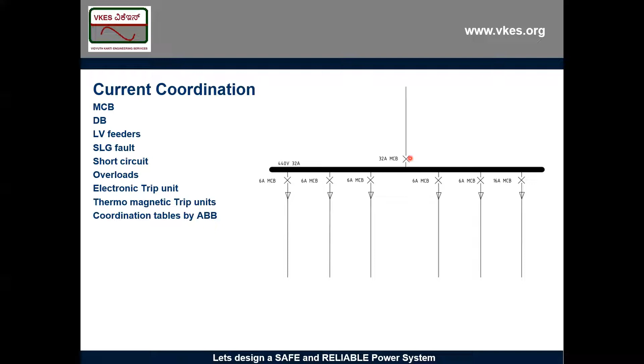And coming back to this time coordination. See here, the coordination is based on time. It means if there is a fault here, first this guy has to trip, then this guy has to trip, then this guy has to trip. One by one, they have to trip. That is why I'm using the word coordination. If there is a fault here, if this downstream breaker trips at, let's say, 100 millisecond, the next upstream breaker will trip at, let's say, 200 millisecond, then this incomer breaker will trip at, let's say, 300 millisecond. So that is what coordination is.